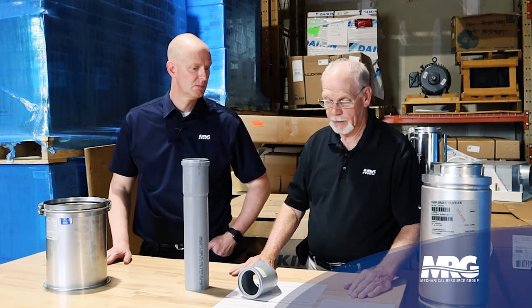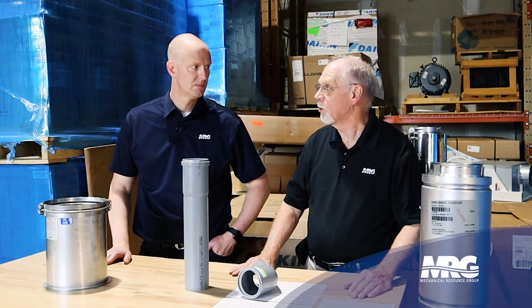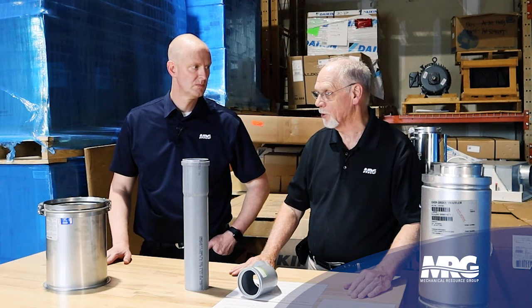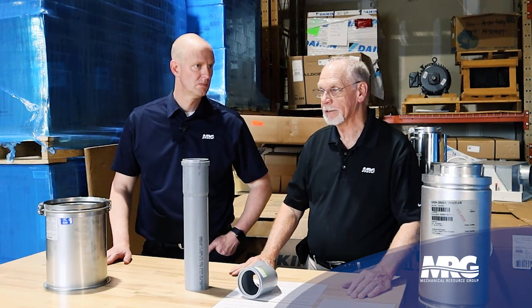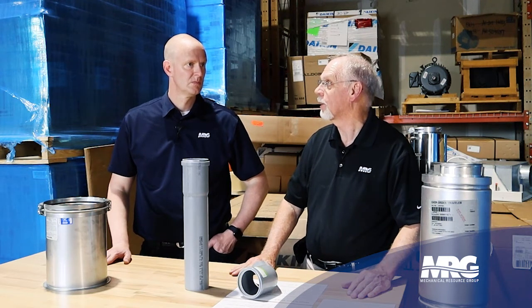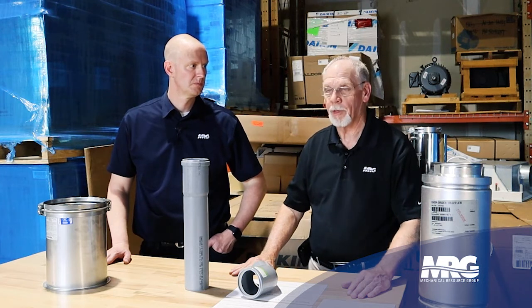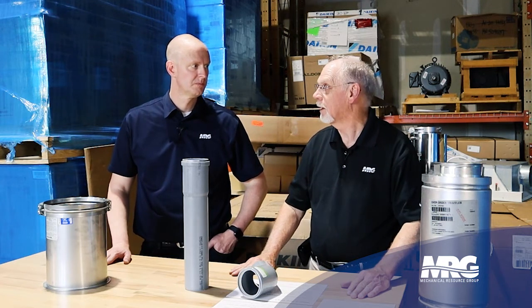Like I say, we have negative pressure for 1 and 2, positive pressure on 3 and 4, and they have different joints to make sure that you do that. Biggest thing is that you want to make sure that the vent gases stay in the pipe until they go out into atmosphere, so that you don't have a problem within the building for safety of all your occupants.